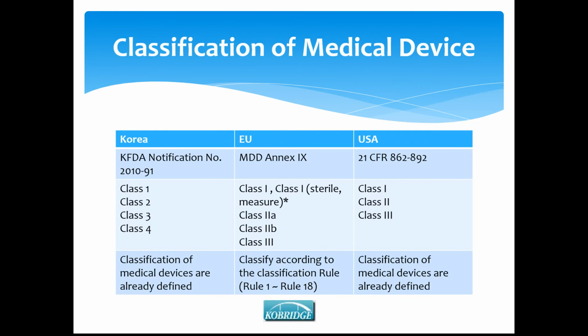Typically in Europe the classification is given by Annex 9. There's a notification, the KFDA notification also, which gives the class of product, and those classes are often updated. I want to go to the classification approach, which is much similar in Korea as in the US, meaning that this classification is already defined. So once we know the category of products, then we know the class. So it's given. It's very detailed. However, if we compare Europe, in Europe the classification should be demonstrated or defined by the manufacturer based on different rules.